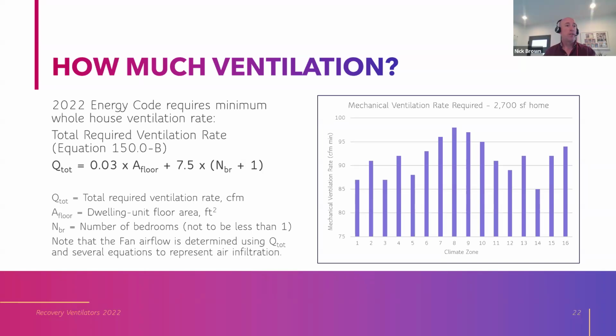We're looking at 85 to almost 100 CFM for a 2,700 square foot home. A few code cycles ago, this would have been 20 or 30 CFM lower. So over time, they've decided higher airflow is needed. And a 50 CFM bathroom exhaust fan is not going to do it, is it? You're going to need 2 bathroom exhaust fans running continuously for this size home. Another reason that recovery ventilators are a great way to go rather than just relying on exhaust ventilation.